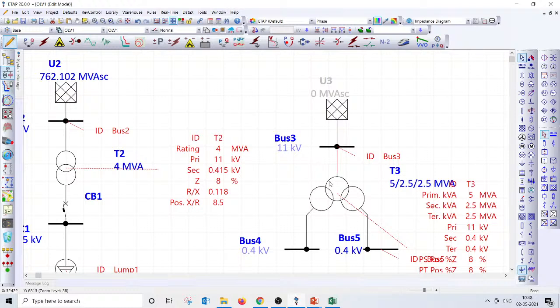Typically, up to 630 amps, people tend to go with an MCCB, not really investing heavy cost on ACB. And at 800 amps and above, people tend to use ACB always. But nowadays a few people tend to use MCCB even for 800 amps and 1000 amps.